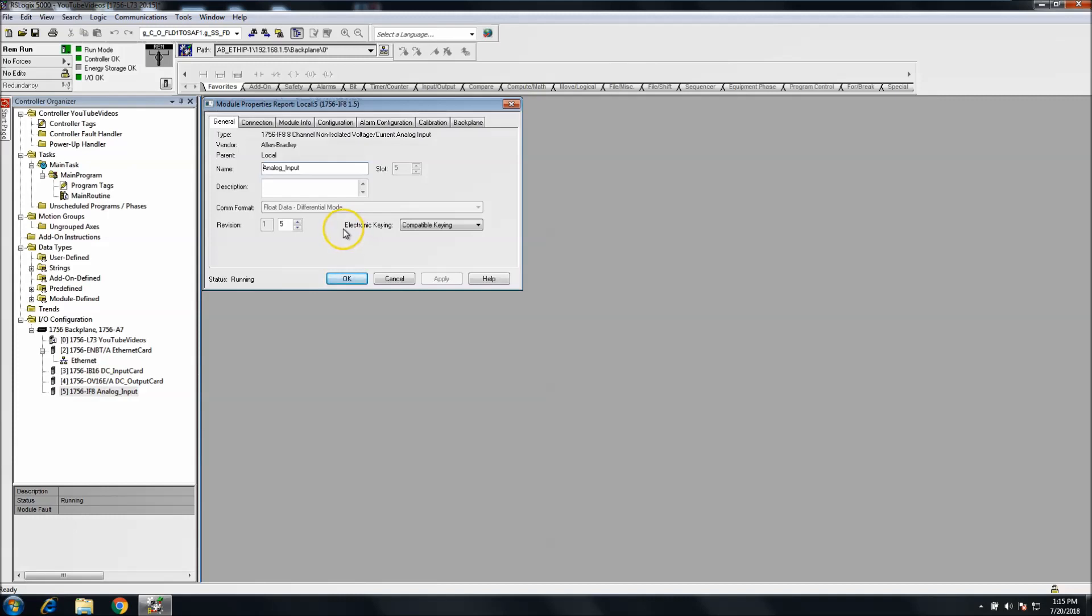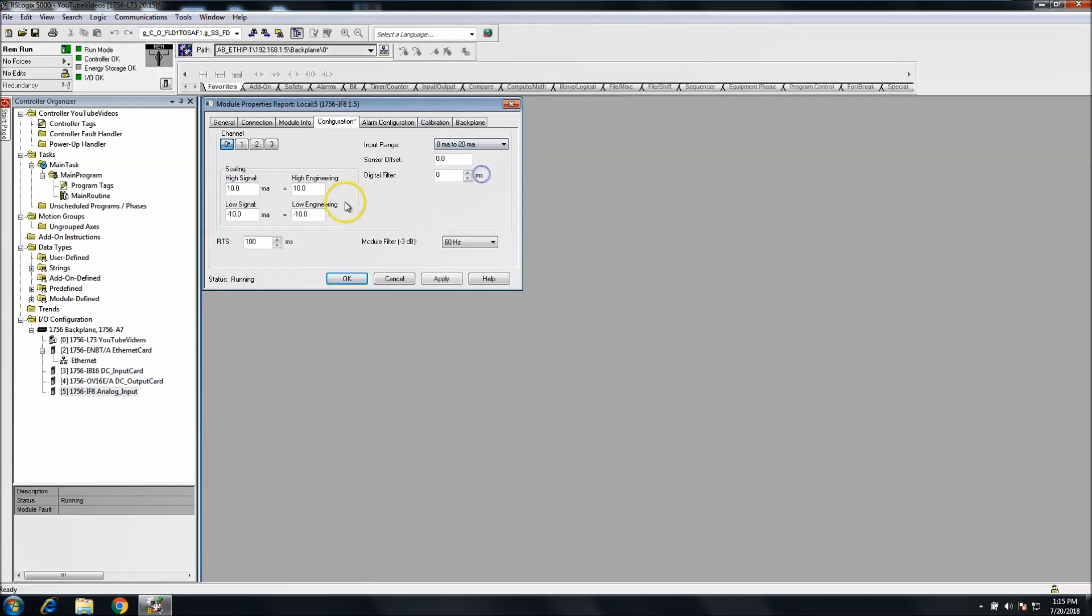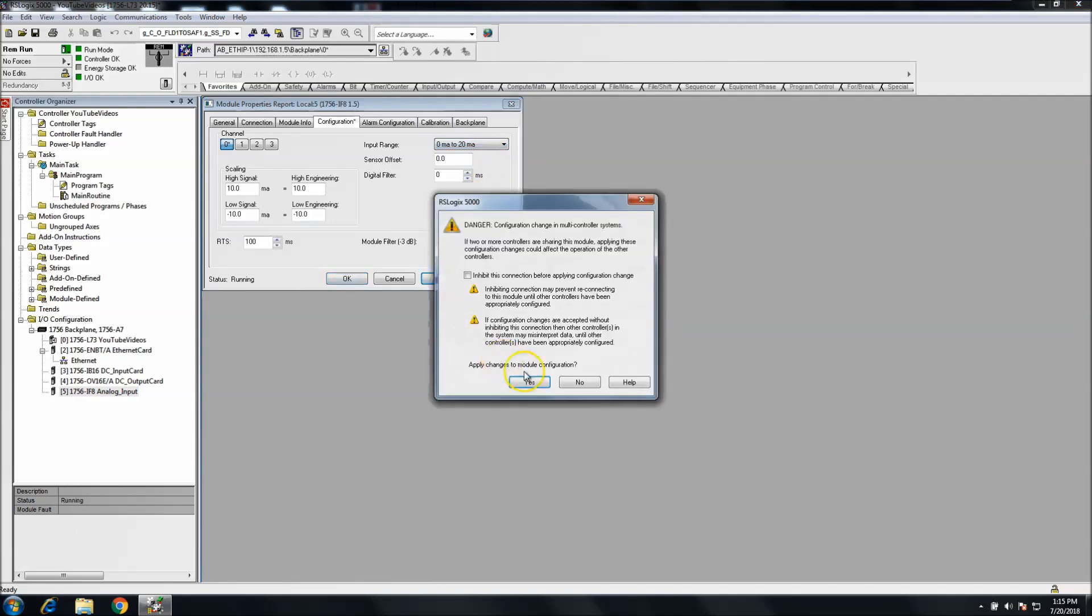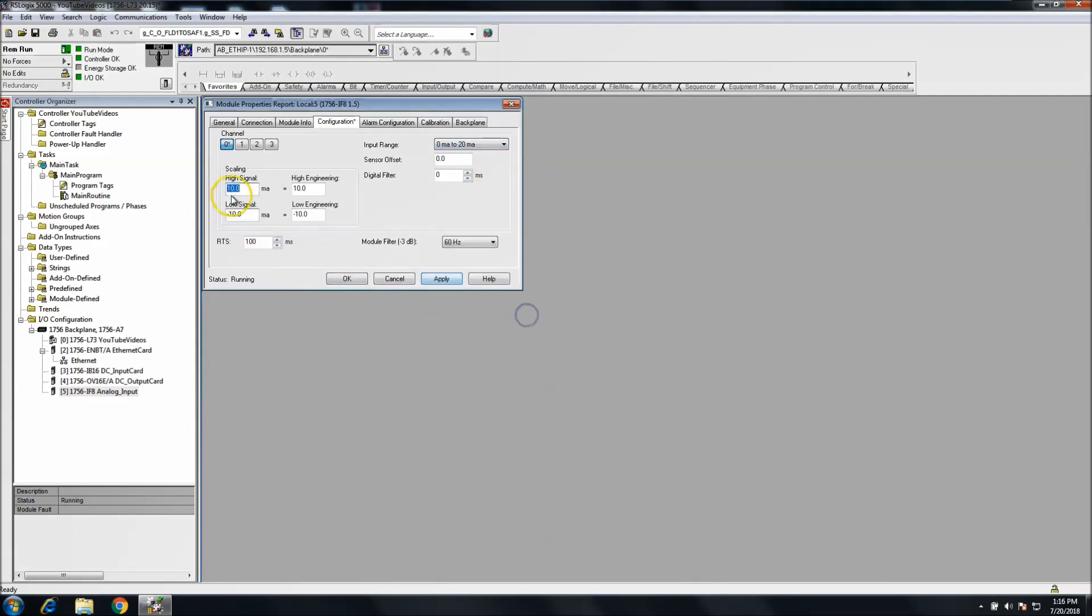If you're using an analog card and you don't want to use zero to ten or negative ten to ten, you want to use four to twenty, then you can't just come up here and select for channel zero, you can't just select four to twenty. If I hit apply, it's going to say it's not right. What I need to do is change my engineering units to match.